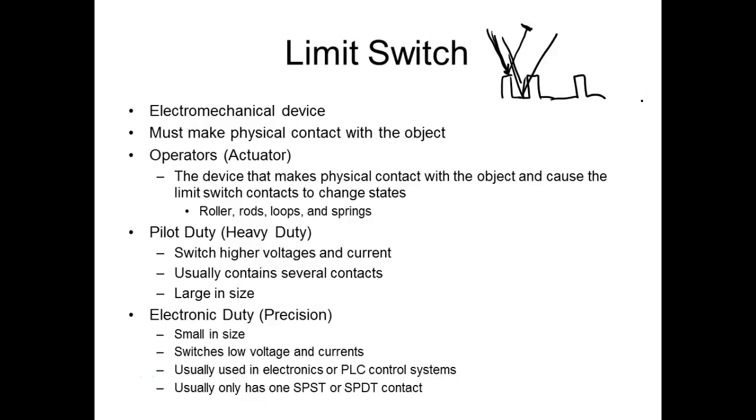Then we have what we call electronic duty switches. These guys are not designed to run loads. These guys are designed to give us a voltage or not a voltage that we would input into a PLC or something like that. That's the PLC. So pilot duty switches higher currents and voltages, usually contains several contacts, and these guys are going to be large in size.